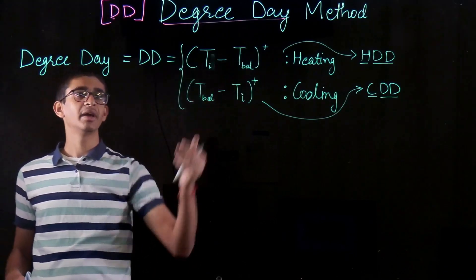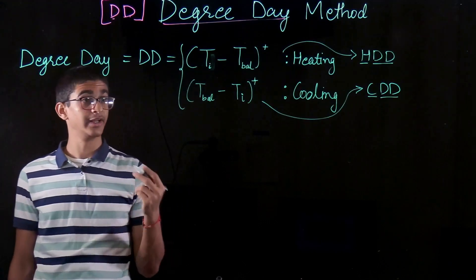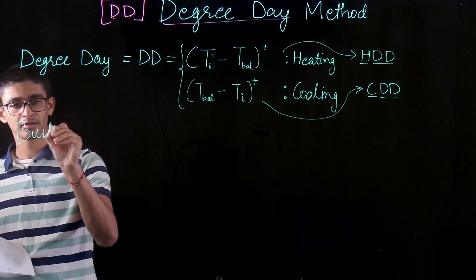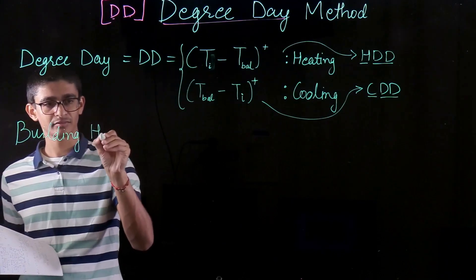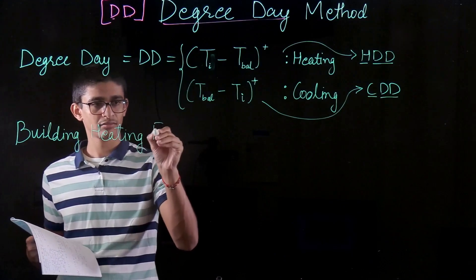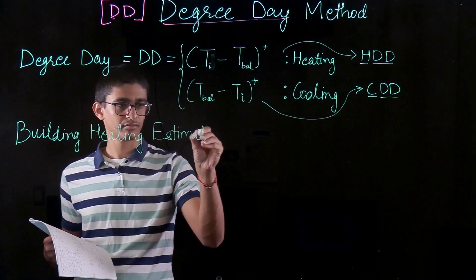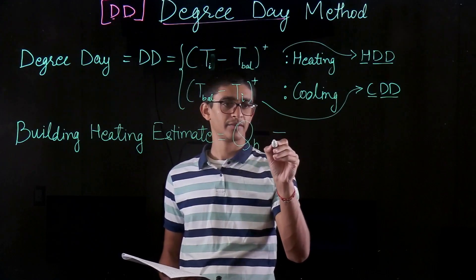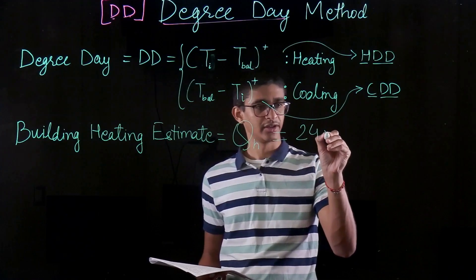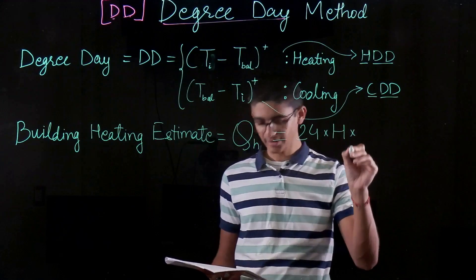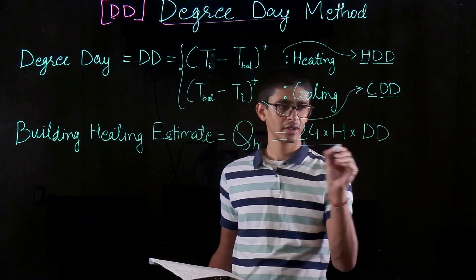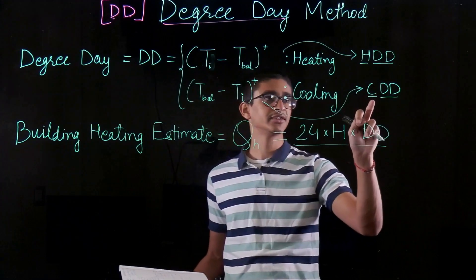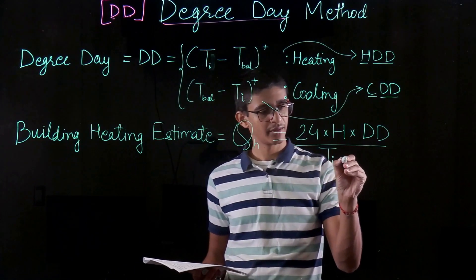The degree day method helps us estimate heating loads — the building heating estimate. It is represented as Q_H (heating) = 24 × H × DD / (T_i − T_out), where DD is the heating degree days. For a cooling estimate, we would use CDDs instead.